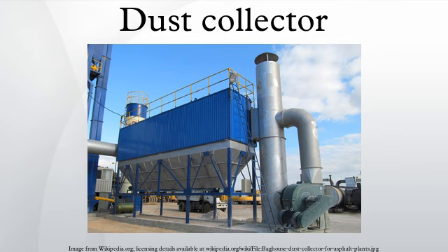Types of precipitators. There are two main types of precipitators. High voltage, single-stage precipitators combine an ionization and a collection step. They are commonly referred to as Cottrell precipitators. Low voltage, two-stage precipitators use a similar principle. However, the ionizing section is followed by collection plates. Described below is the high voltage, single-stage precipitator, which is widely used in minerals processing operations. The low-voltage, two-stage precipitator is generally used for filtration in air conditioning systems.